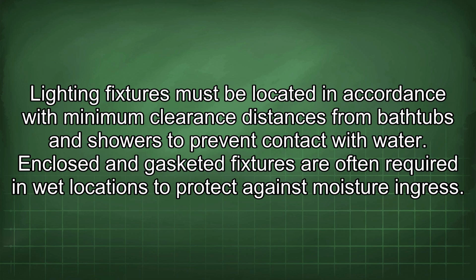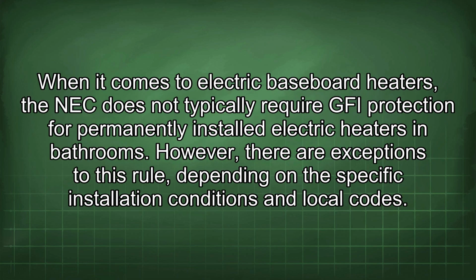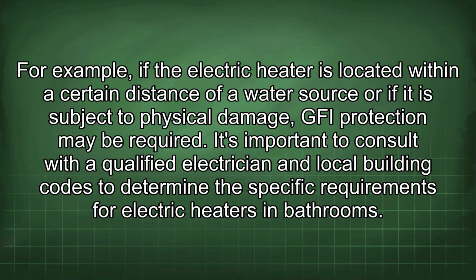Enclosed and gasketed fixtures are often required in wet locations to protect against moisture ingress. When it comes to electric baseboard heaters, the NEC does not typically require GFI protection for permanently installed electric heaters in bathrooms. However, there are exceptions to this rule depending on the specific installation conditions and local codes. For example, if the electric heater is located within a certain distance of a water source or if it is subject to physical damage, GFI protection may be required.